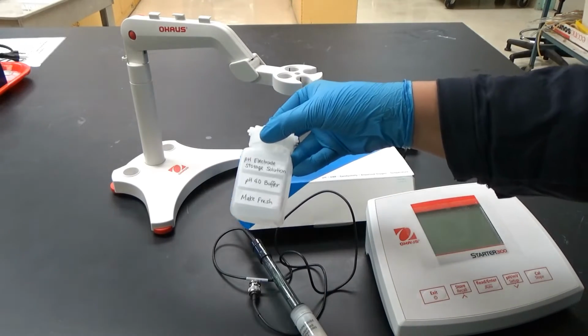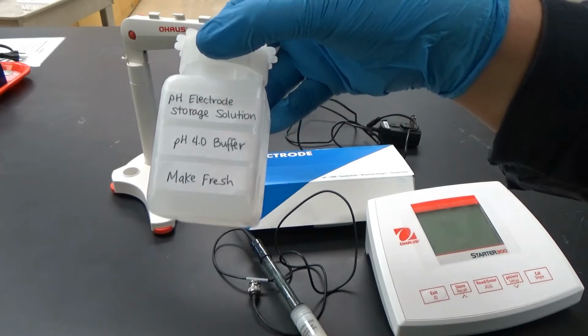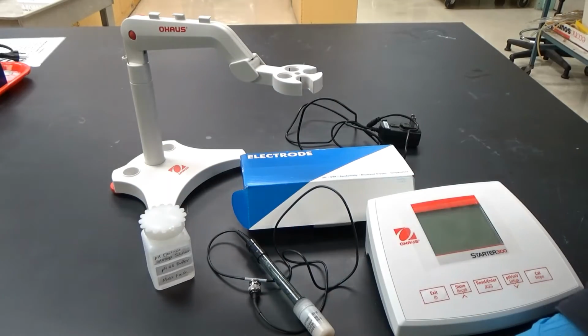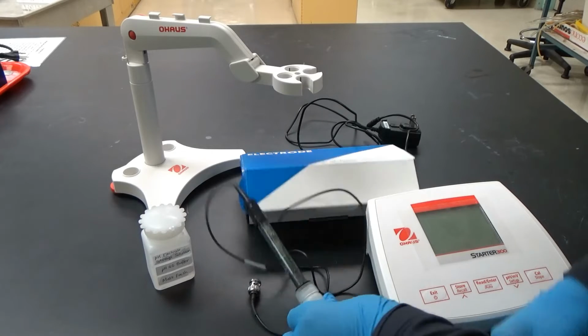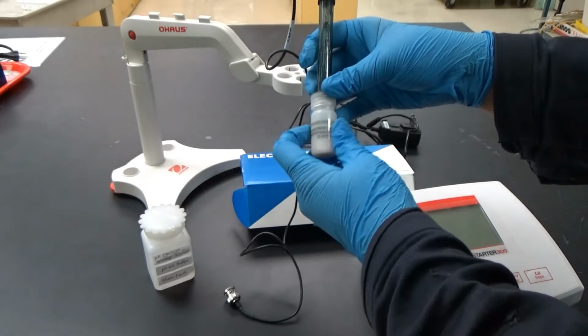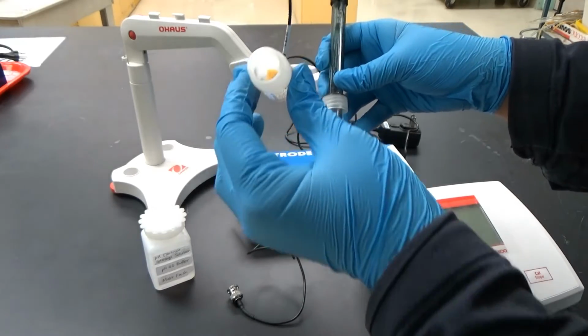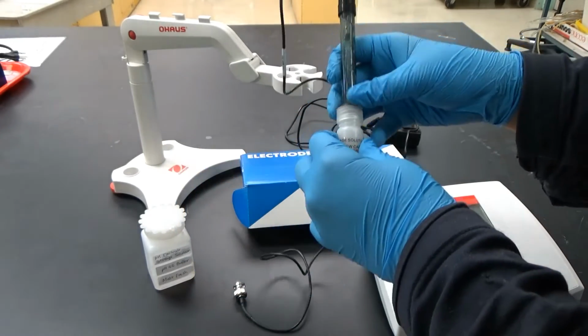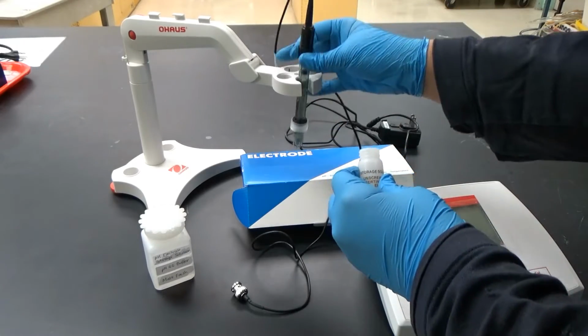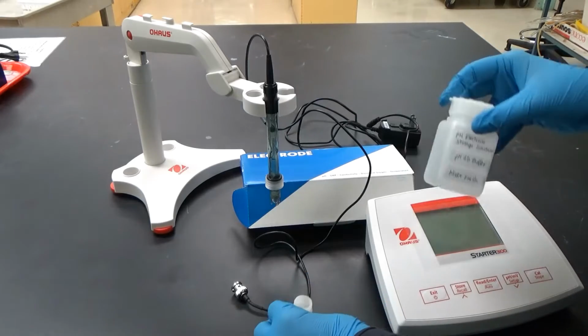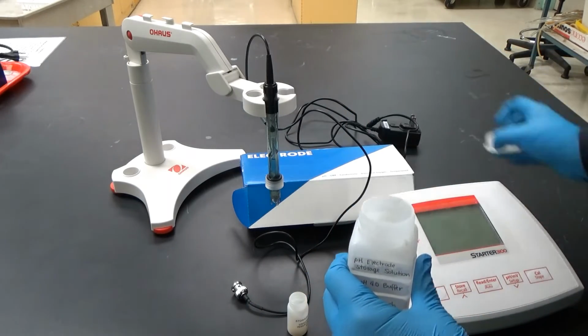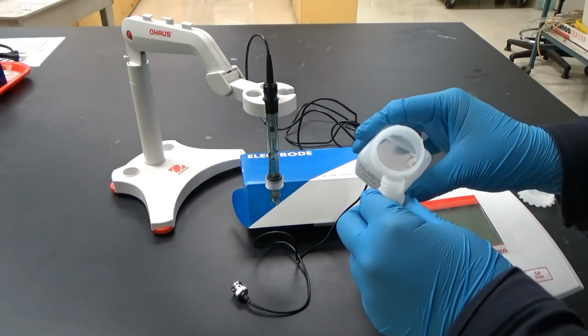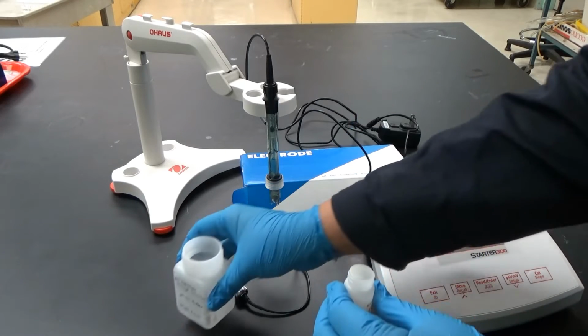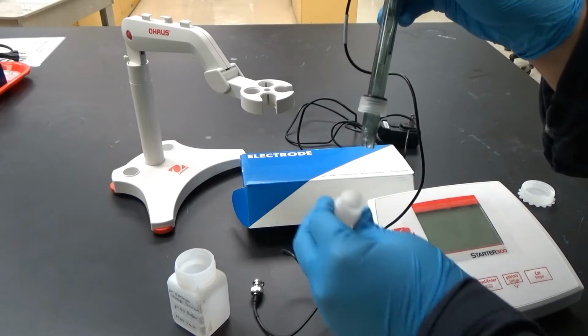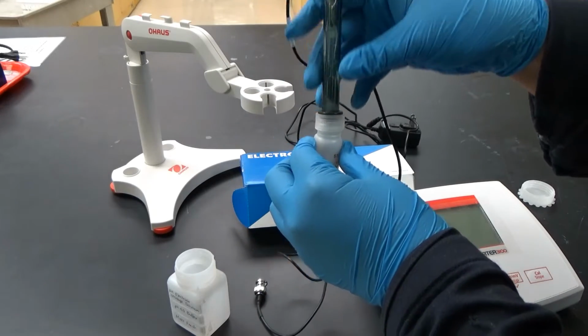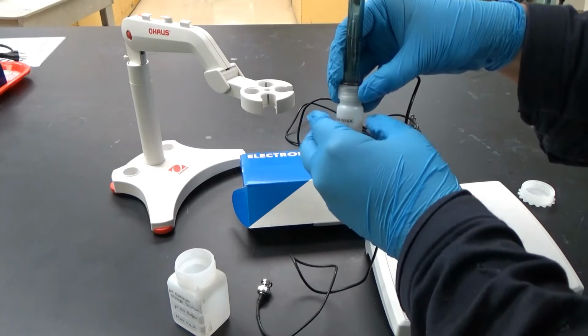And on the cart will be the pH electrode solution for you to refill the electrode. Sometimes the electrode might be a little bit dry inside, so make sure you check this part. It has a little sponge inside, and if it's dry, you want to refill it with some pH electrode storage solution. You cannot let the pH electrode go dry because it affects the performance over time. So you always want to soak it with a little bit of storage solution so that it doesn't dry out.